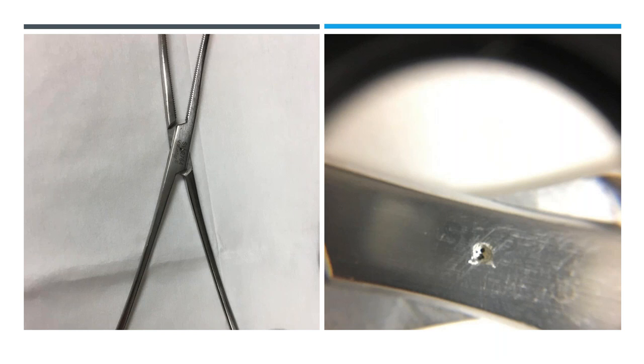That's a pitting problem, and that pitting problem could lead to all kinds of problems with the cleaning process and potentially pose a risk to the patient, and also to the device itself, compromising it and making it more prone to breaking. So lots of issues there that you may or may not see with the unaided eye.